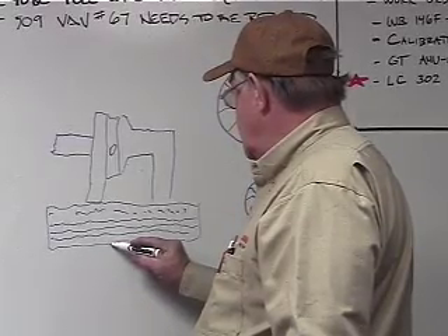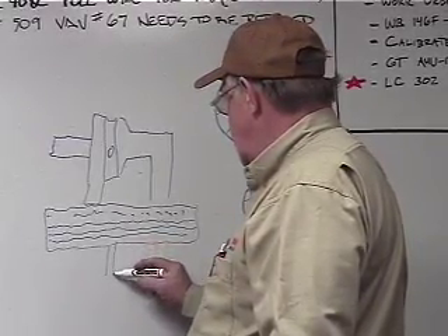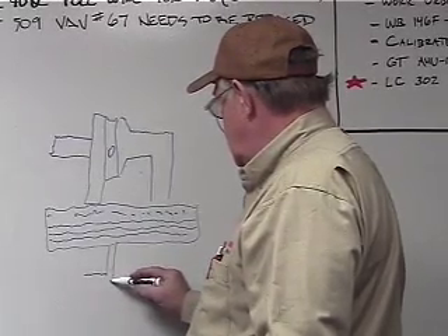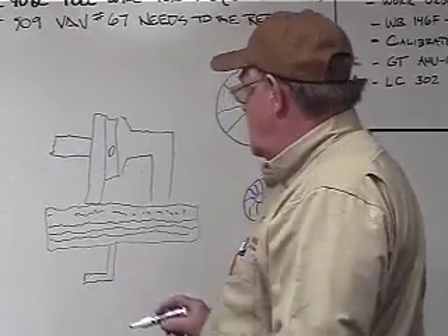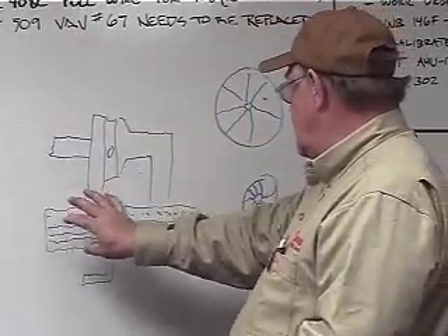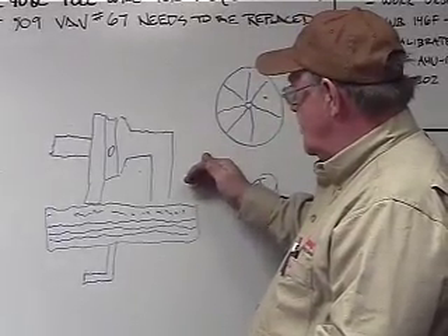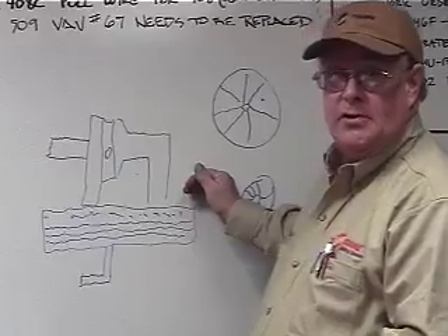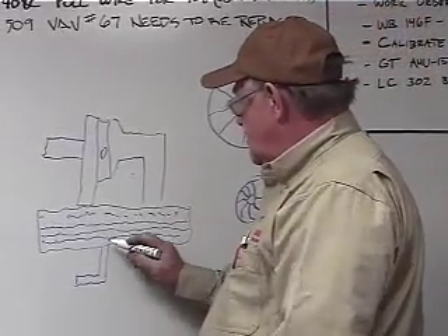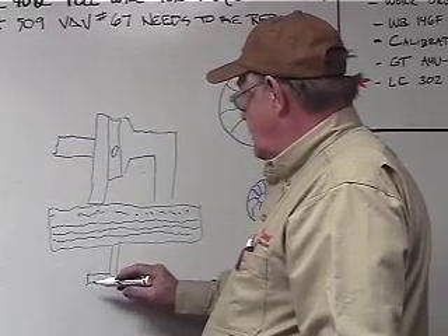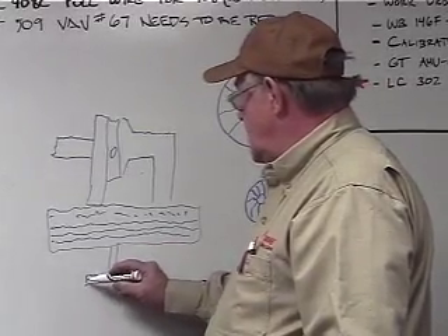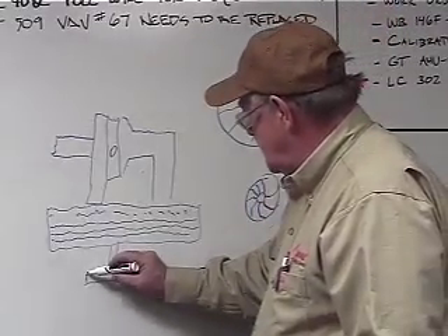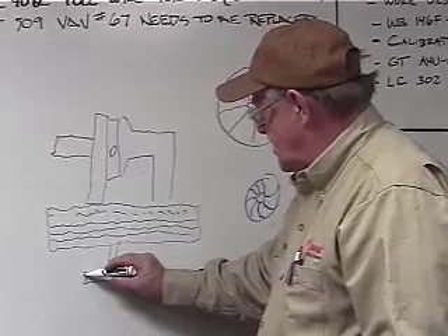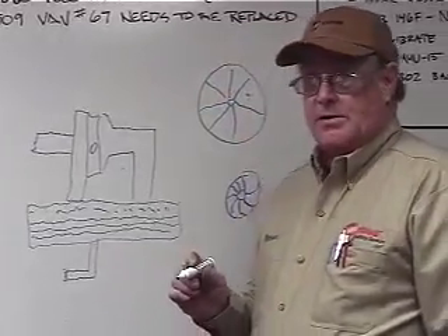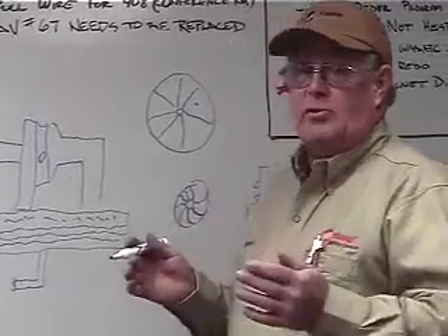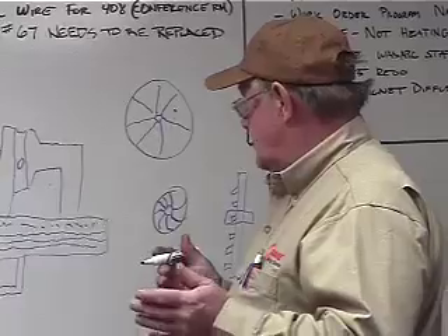And at the bottom in the center, you're going to have something that looks like this. So what happens is your condensing water goes through, it condenses your refrigerant, high pressure refrigerant gas into a liquid. As it goes through, down through your drip leg or your liquid of your condenser, there's going to be another one of those orifices right here. So it's got the little holes, things like that. So actually that's starting to break up your liquid pressure, your liquid refrigerant.